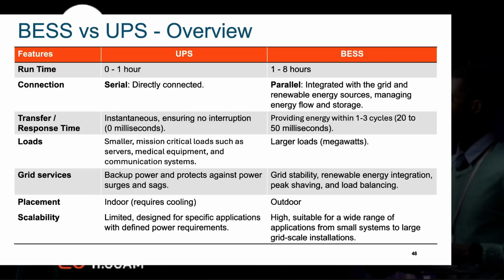Grid services: UPS can act as backup and protect against power surges and sags. But BESS can be used to stabilize the grid, because the data center itself, in some cases, is a big campus hooked to the grid, and you don't want issues. With a BESS solution, you're able to stabilize the grid because you have other energy sources or a mix of energy within your facility.